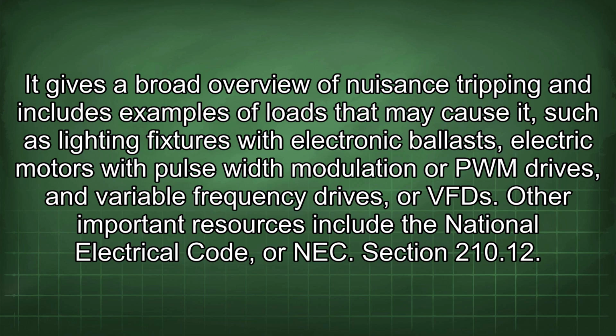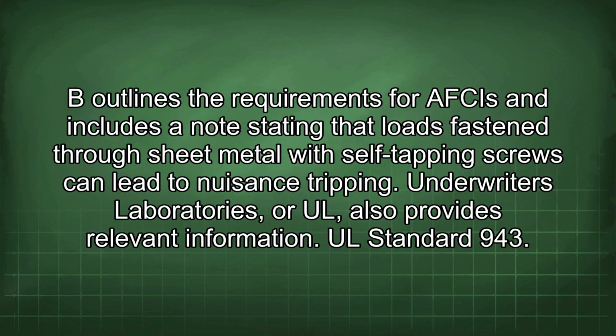Other important resources include the National Electrical Code, or NEC. Section 210.12 outlines the requirements for AFCIs and includes a note stating that loads fastened through sheet metal with self-tapping screws can lead to nuisance tripping.